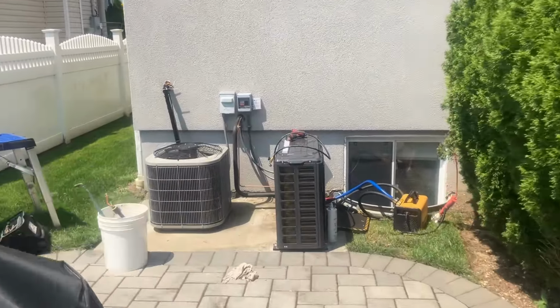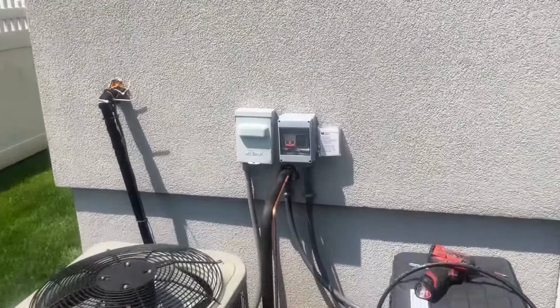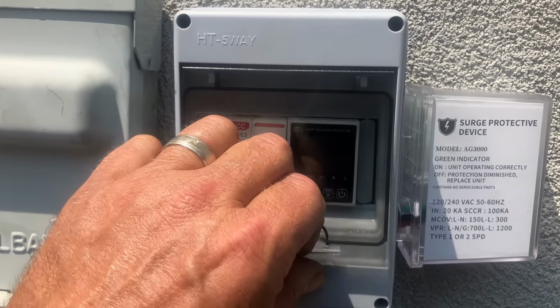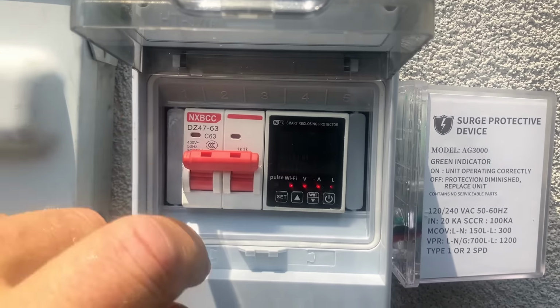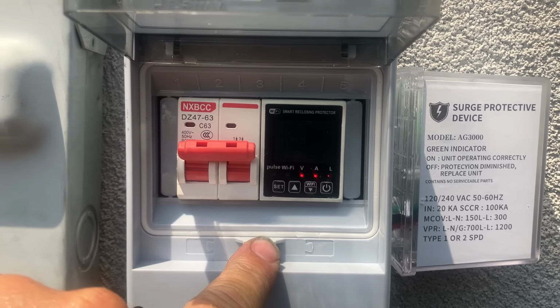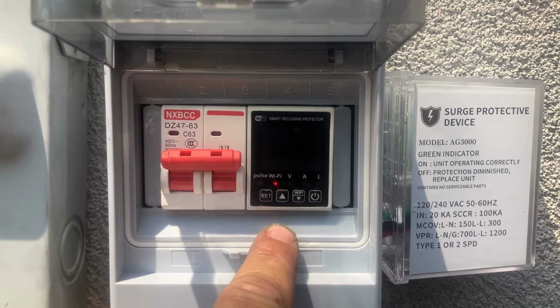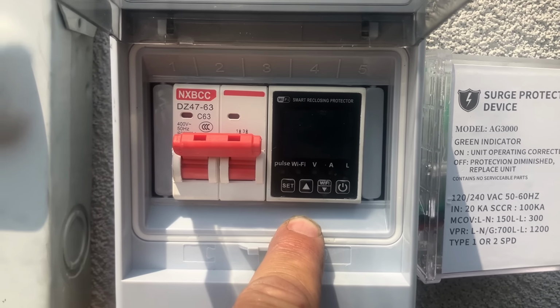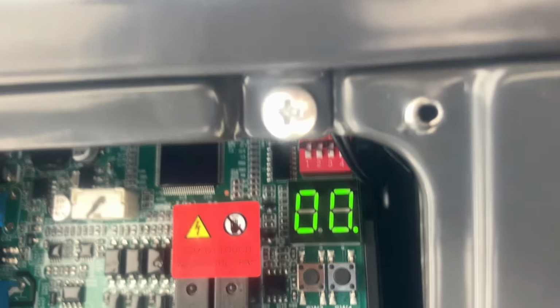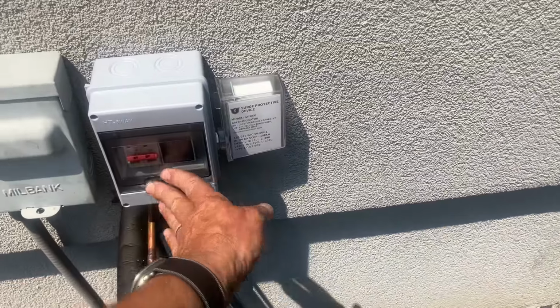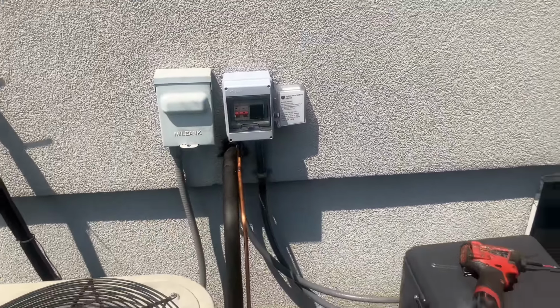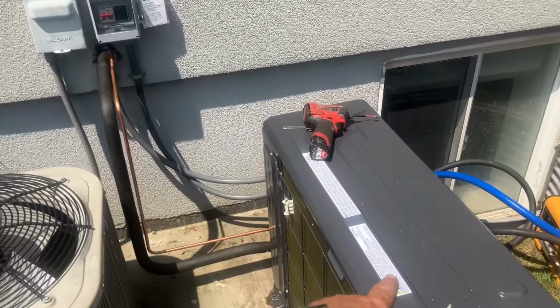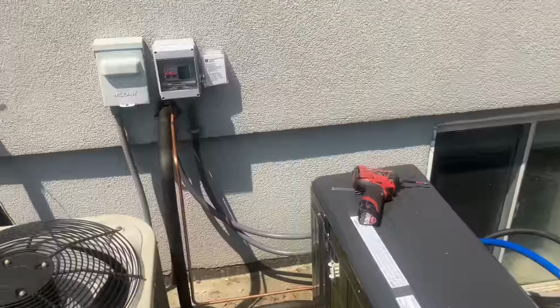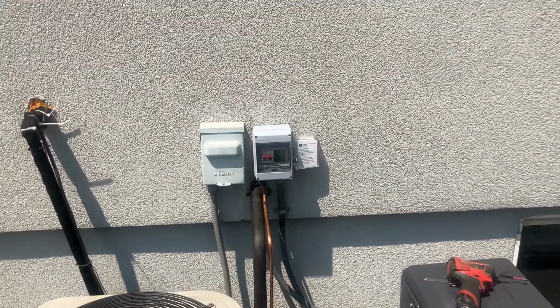All right, Daniel gave me the go-ahead to fire up. All right, the voltage range monitor and protector is powering up. We have an illuminated control board, and we also have an active call for cooling right now. So in a few moments, the condenser fan motor will come on, and then our inverter driven compressor.